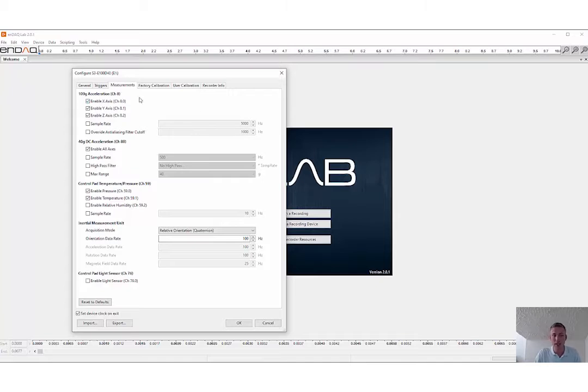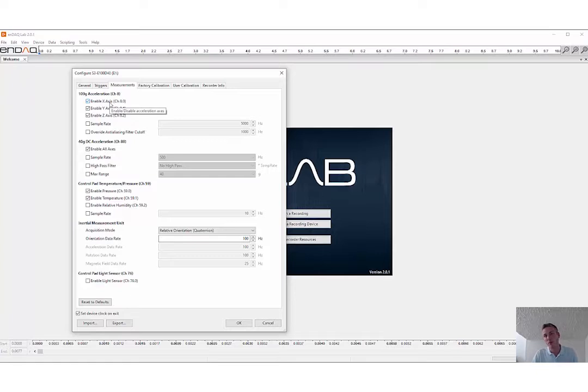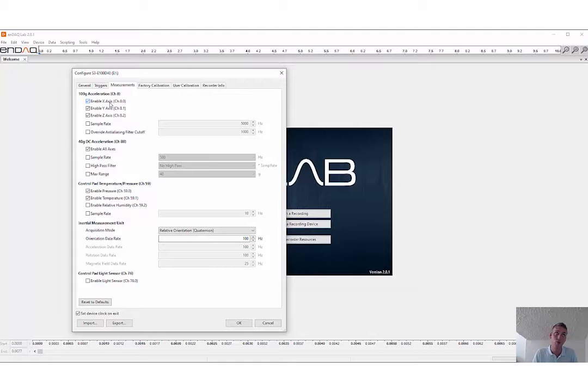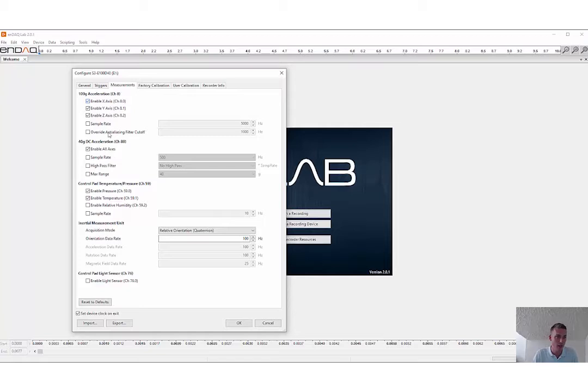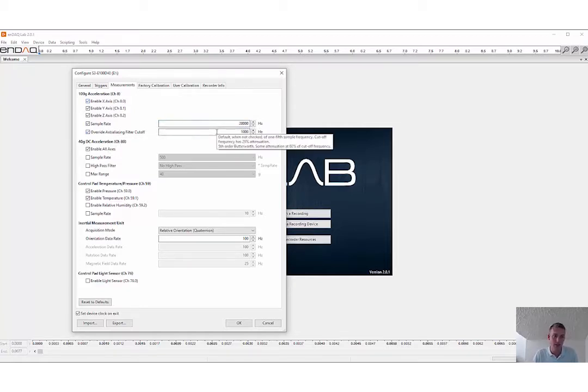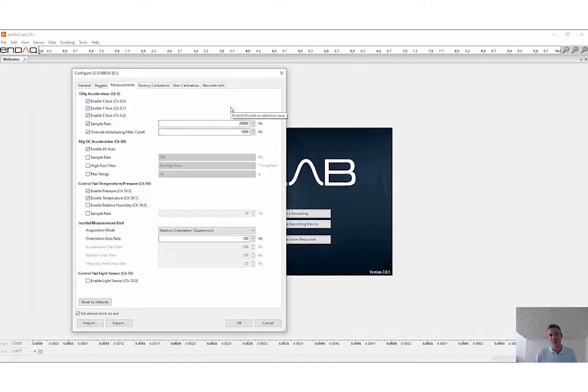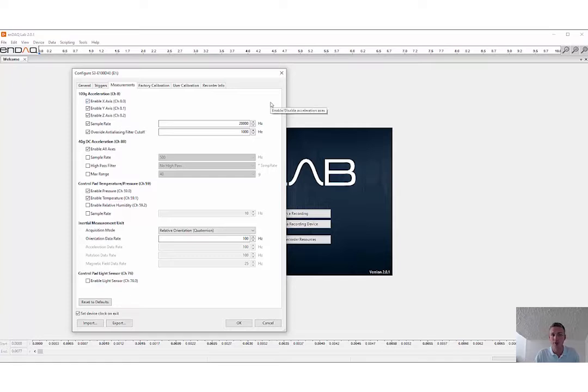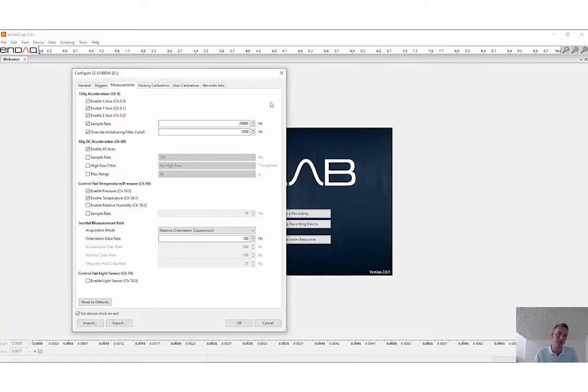The first area is that main accelerometer. You can enable a certain number of axes if you want, and this can improve battery life as well as storage capacity by only recording a handful of channels if you like. But the sample rate will go up to 20 kHz, and then this is the anti-aliasing filter cutoff as well as a low-pass filter so you can get rid of high-frequency noisy data.